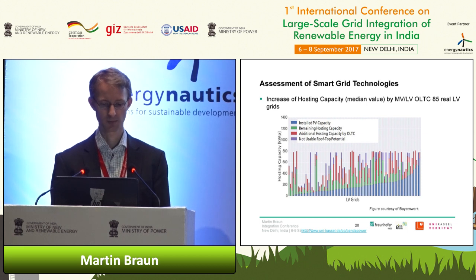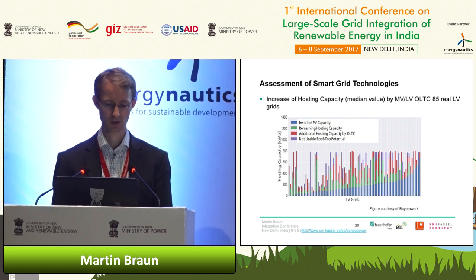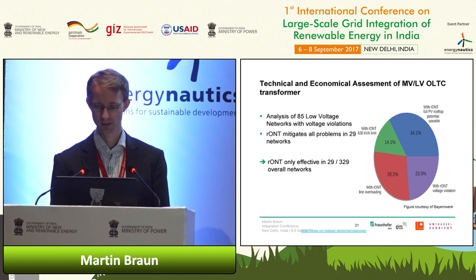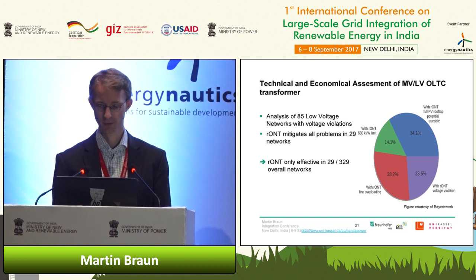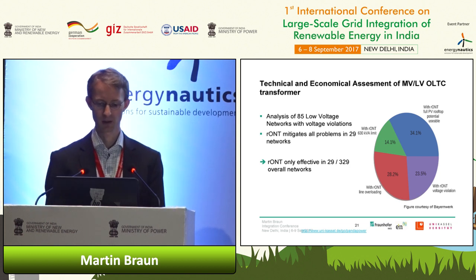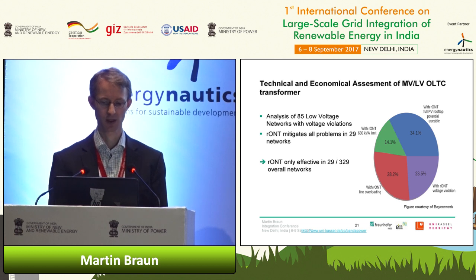In some grids there's still potential for additional power to be installed, since the rooftop potential isn't fully used yet. Analyzing this, with the on-load tap changing transformer, the full potential can be used in a third of the cases. In other cases we hit limits related to transformer size, and in one quarter we still have voltage violations, and in another quarter line overloadings, so we need other solutions.